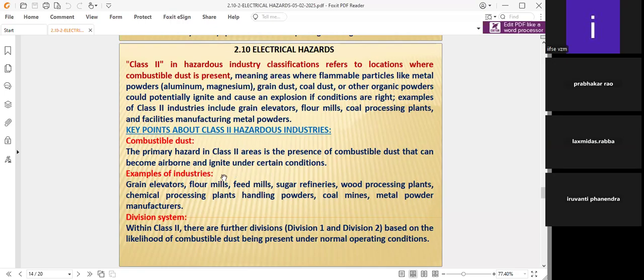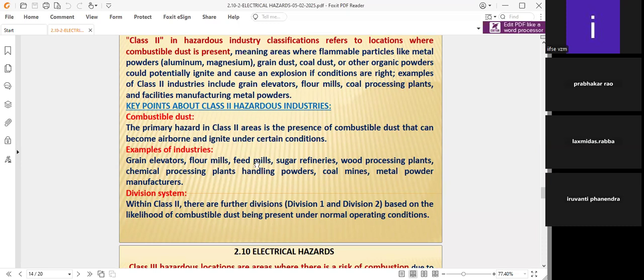The examples of industries of class 2 areas: grain elevators, flour mills, feed mills, sugar refineries, wood processing plants, chemical processing plants handling powders, coal mines, and metal powder, where the dust is very ignitable in nature. Therefore, it is very important to take care. Hazardous areas are there because of class 2. You have to see that all the electrical circuits, all the electrical panels, and all the electrical equipment are properly installed, insulated, and taken care of, not to be dust prone, not to be exposed to the dust. All these panels, electrical circuits, and electrical equipment in these industries, especially.